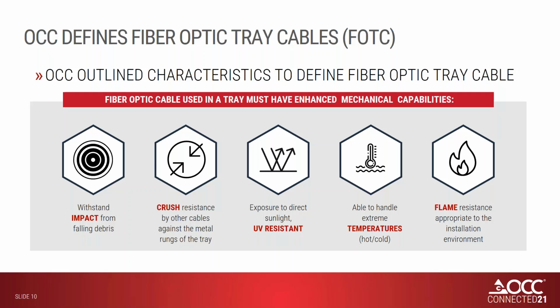So how are you applying this cable? What are you putting it in? And we took these requirements and determined that fiber optic tray cable must address these 5 features. They must be able to withstand impact from falling debris, have a high crush resistance by other cables. They must be able to be exposed to direct sunlight and have UV resistance, able to withstand extreme temperatures, hot and cold, and have flame resistance for the application. So this could be either a riser rated or a low smoke zero halogen rated, and we do have both. OCC's definition of fiber optic tray cable exceeds all industry standards and our competition. So let's look at the three types of cables that we offer.